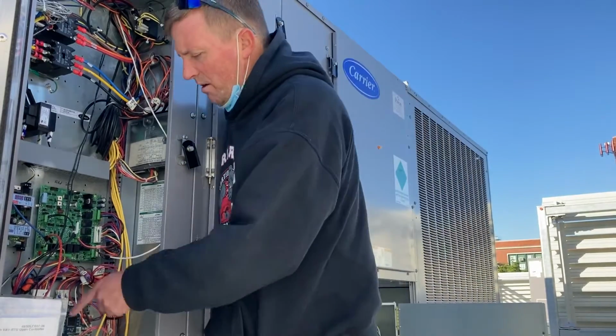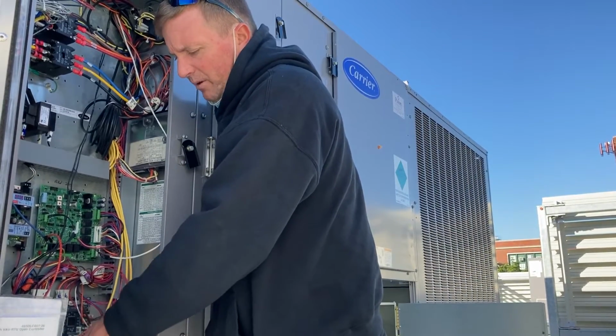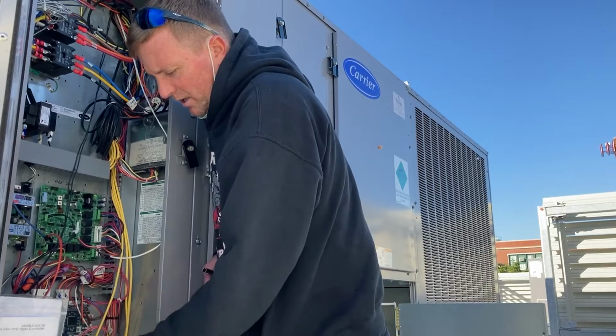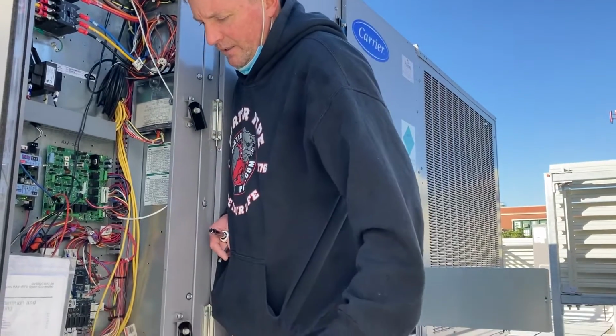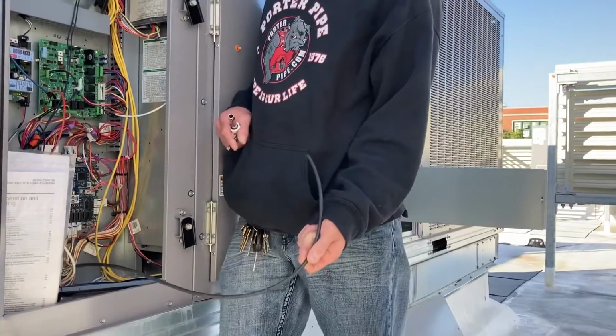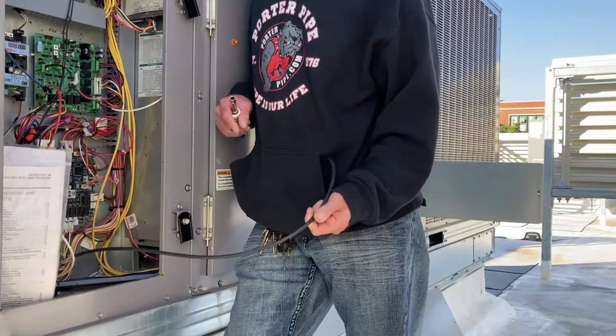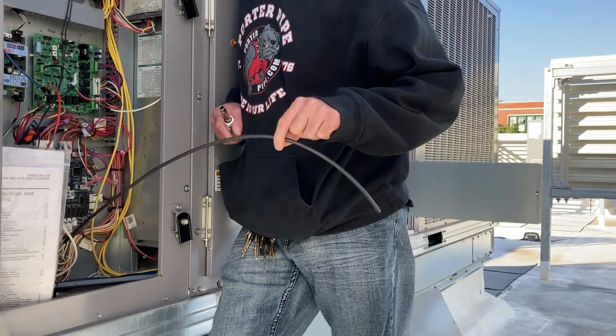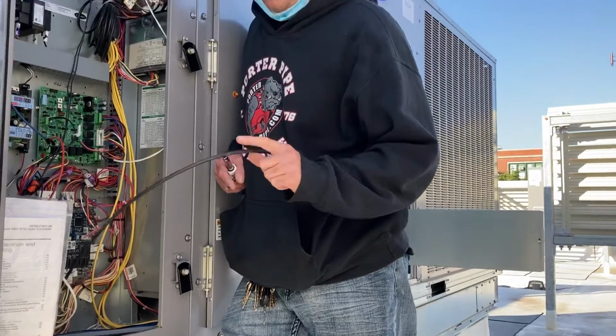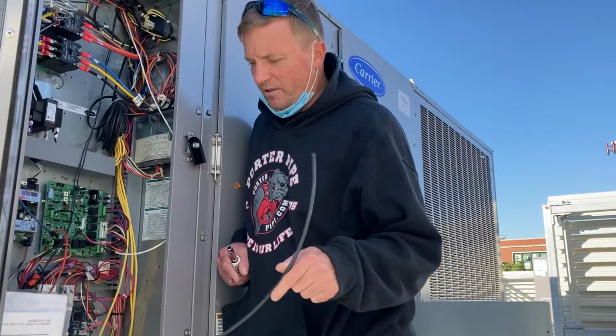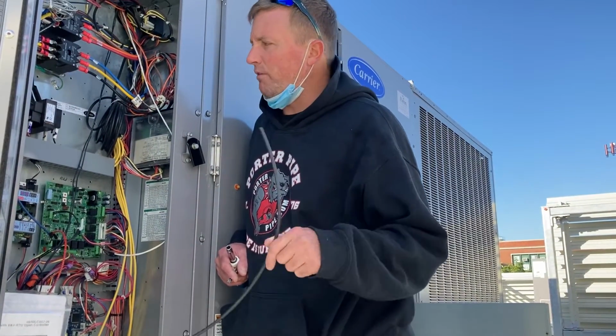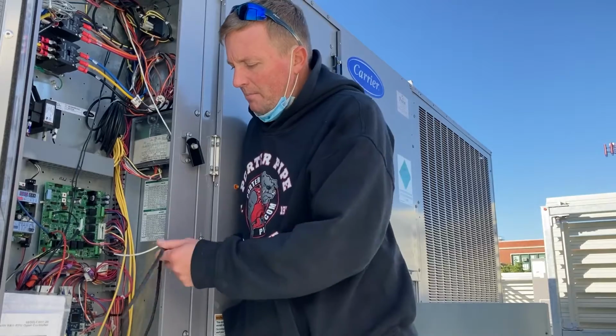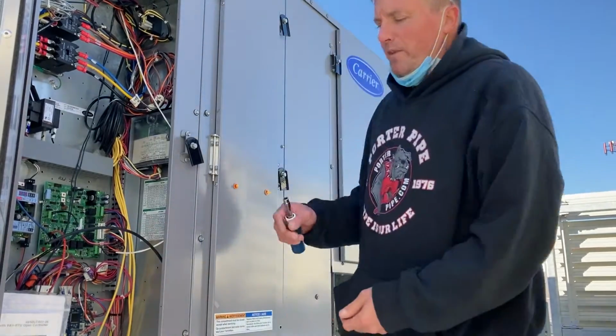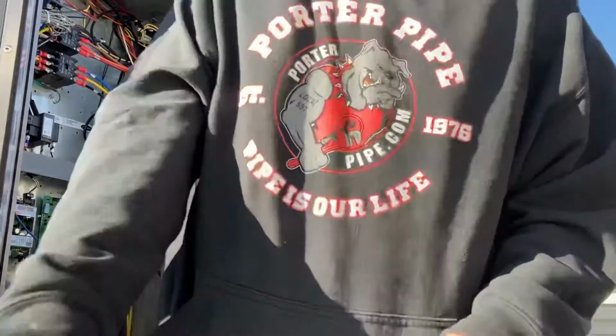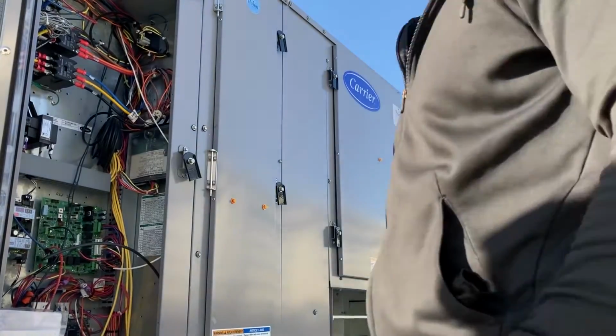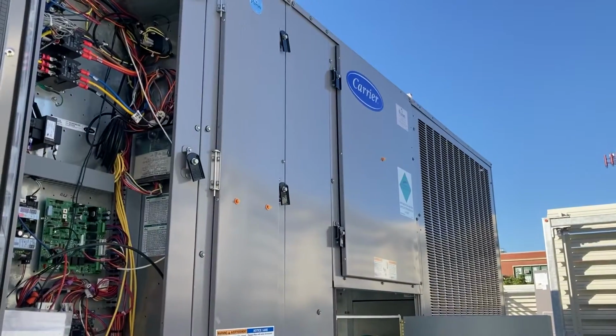That also being that we have building pressure as well here. I don't see the building pressure sensor, so we need to look at this. We need to talk to whoever to figure out if the BAS contractor is installing it or if we needed to supply it. But basically, when the building pressure gets higher, that's what the power exhaust is.